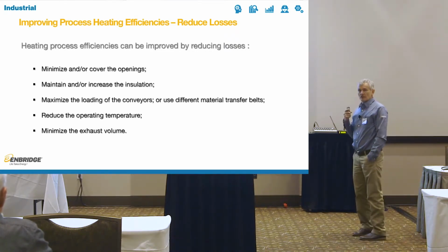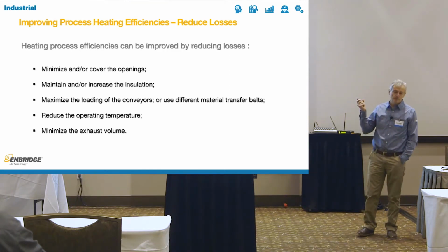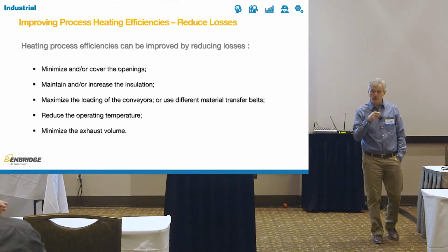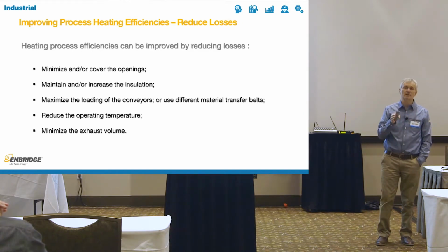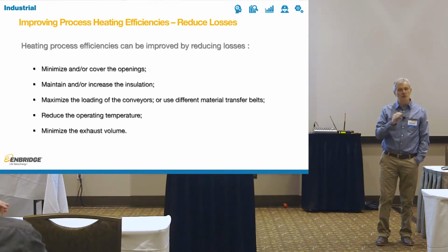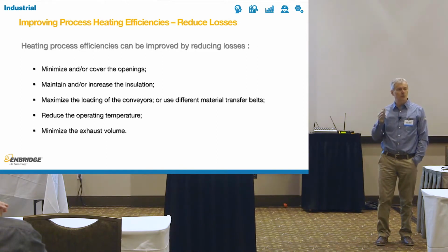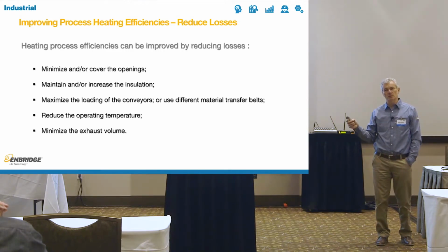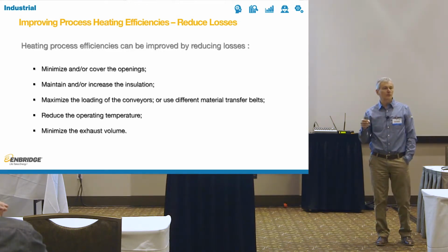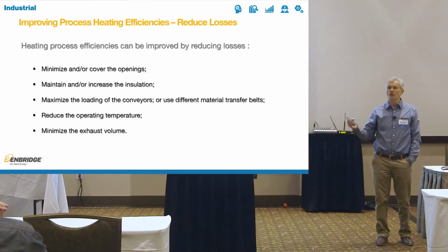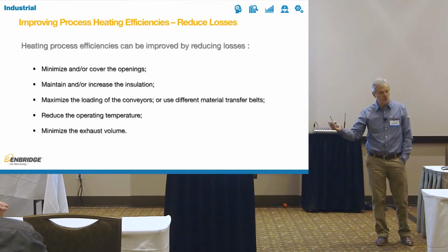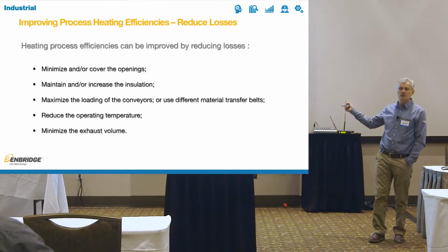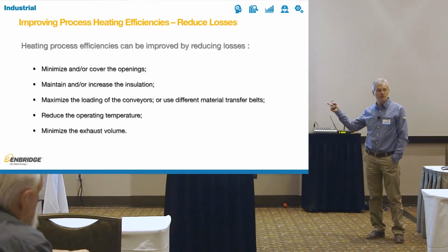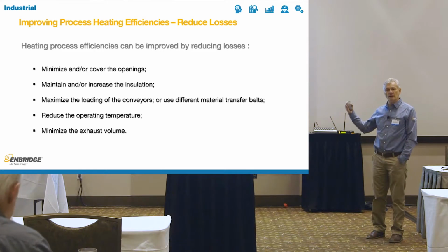Reduce the operating temperature. This happens a lot. Over time, we all are nowadays working under lean conditions. There aren't that many of us in the facilities anymore. Maintenance is stretched to the maximum. Over time, these ovens don't operate as they used to. They get plugged up. For the operator who is responsible for turning the widgets out, the best way to deal with that is just to turn up the temperature a little bit. So the set point of 375 at one point is now 450, and nobody cares because the widgets are going out. Well, that 450 versus 375 generates a lot of heat losses. So take a look. Maybe it's worthwhile cleaning that oven every now and then.